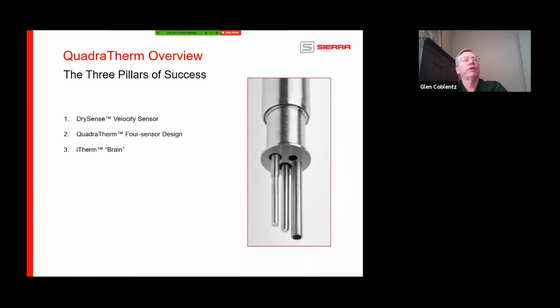The whole success of the Quadratherm rests on those sensors that you see. You have the dry sense velocity sensor, which is the sensor with no organics in it, lifetime warranty on that sensor. You have a 4-sensor design in terms of temperature, and you have the iTherm brain that does all of the calculations for you. Here's a close-up picture of it. This is the actual velocity sensor. This is a standoff sensor to keep you from breaking the sensors as you install them into the field, and this is just measuring what the ambient temperature is.